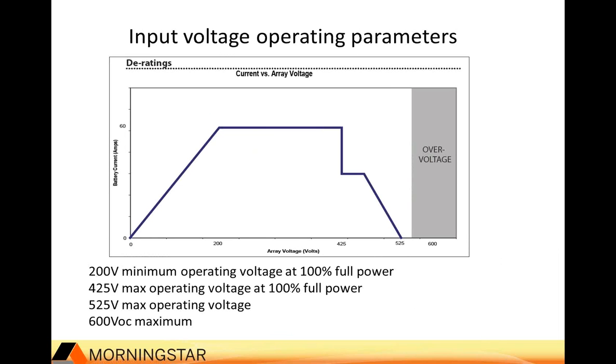Talking a little bit about the input voltage parameters, this product does operate at a very wide input voltage range, and I just wanted to give you a little bit of background info. This is a graph from the manual. It has a 200 volt minimum operating voltage, and that is at 100% full power. So it will actually operate below that point. You just get a linear derate, as you can see on the graph. The maximum operating voltage at 100% full power, 60 amps output, would be 425 volts. It can continue to operate up to 525 volts, but again with a derate.